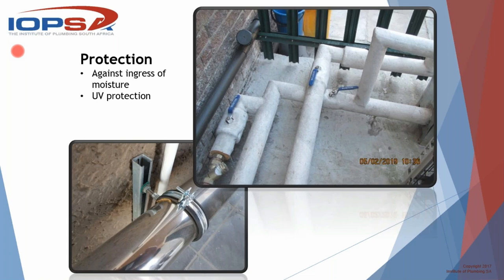And when moisture gets in between lagging and the pipe, it has the same effect, and a little bit of wind, you know, it's the wind chill factor. You jump into a pool with your shirt on and then get out and walk around and the wind's blowing a little bit, you're going to get very, very cold very quickly. That's the shirt absorbing or sucking the heat away from your skin. It's the same effect with the lagging. So in as much as the lagging is an excellent insulator of the pipes, if it gets wet and then the wind starts blowing over it and it's unprotected, it has the opposite effect. Okay, so we've got to protect it against moisture and UV.